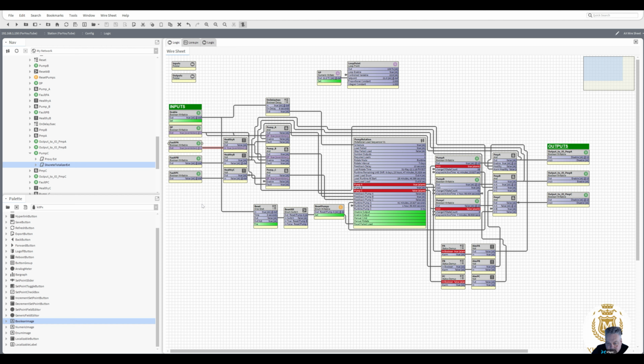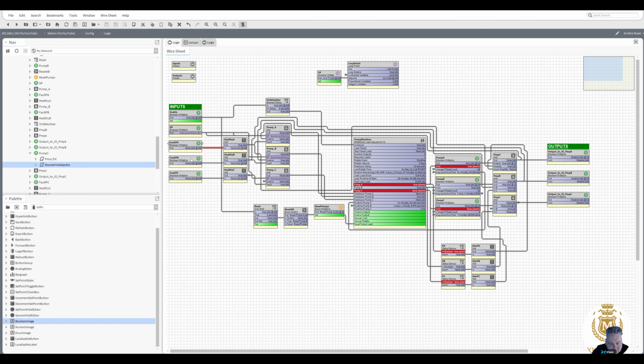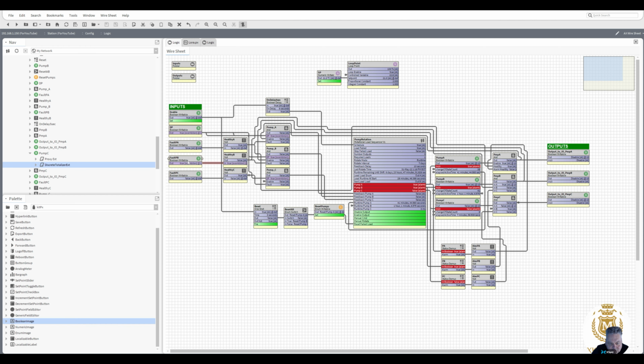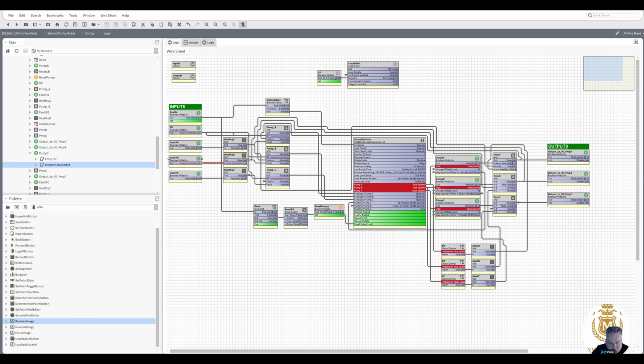Now pump B is running, and it will stay running. We haven't got an output there. We've got an output there. We haven't got an output there. Put pump B into fault. Pump A is now running. No, none of them are running because they're all in fault. They're all in fault. Good.